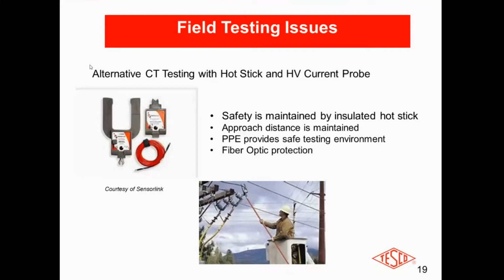It's definitely a practical approach, and I've seen a number of companies start to adopt this because they already have this equipment. Safety is maintained by the hot stick itself. You've got the approach distance, PPE providing protection, and the fiber optic is enormously insulated. Looking at something like SensorLink, it's about 100 kV per foot, which is huge.